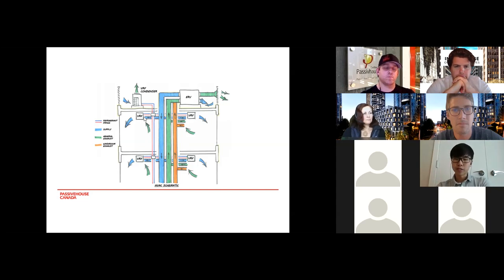Another thing I want to point out is that the design team, the developer Grosvenor, and the City of Vancouver all wanted to minimize the building's operational carbon, and we believe this electric-based solution was the perfect answer to that. Other benefits of the VRF system include simultaneous heating and cooling, as well as heat recovery, achieved by moving heat from spaces or zones in cooling mode through the BC controller to spaces that require heating. Next slide, please, Prudence.